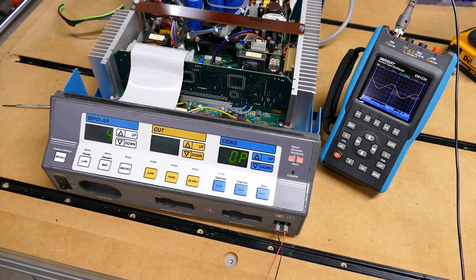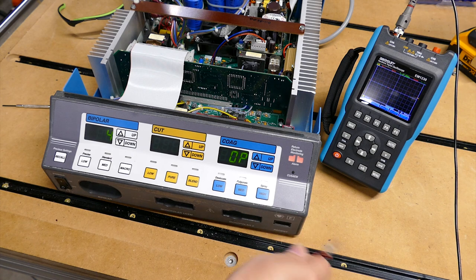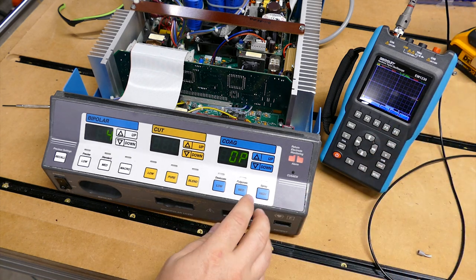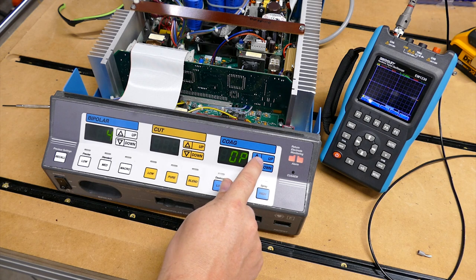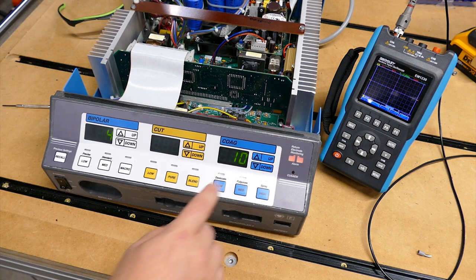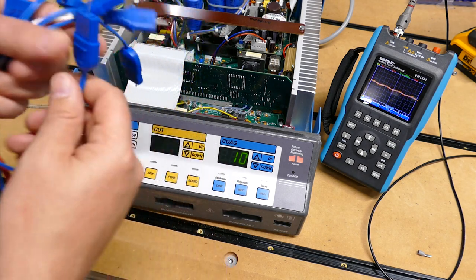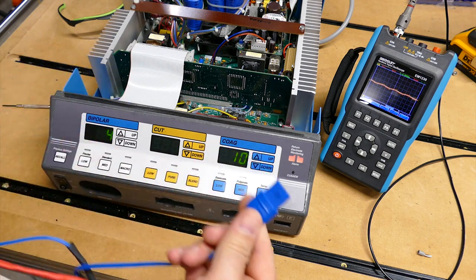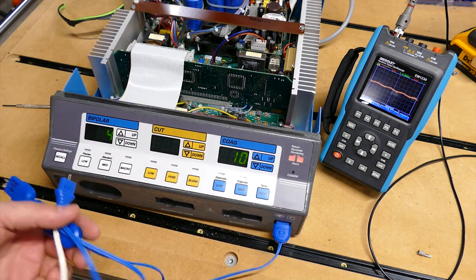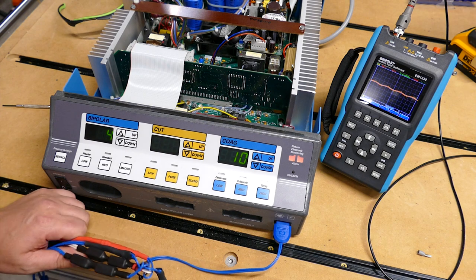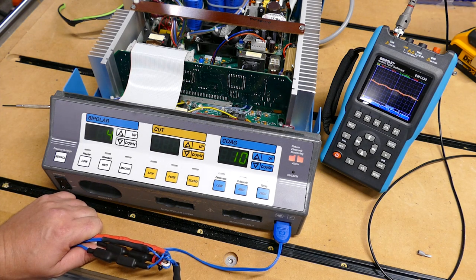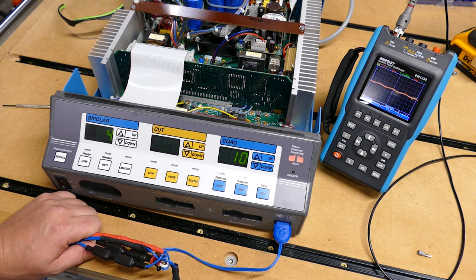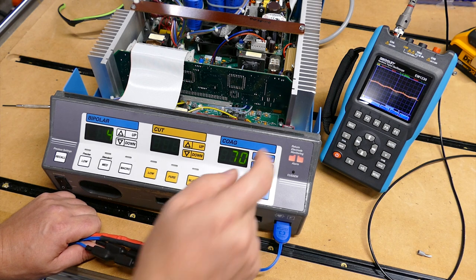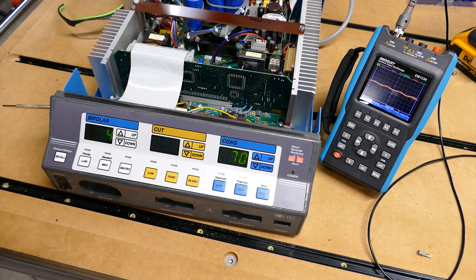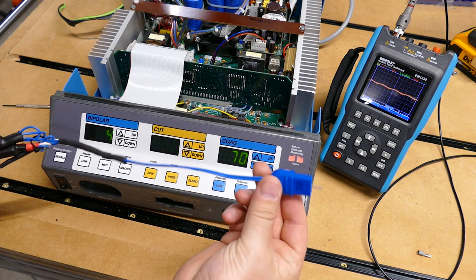Here you can see the front control panel. You're going to disconnect your oscilloscope. And over here are your calibration levels. So you press the up key once and it should say 10. And what you're going to do is find a 10 ohm load and place it here in the calibration port, or your patient return electrode port. I let it sit there for about 10 seconds. And then I press the up key. Now it's asking for 70 ohms.